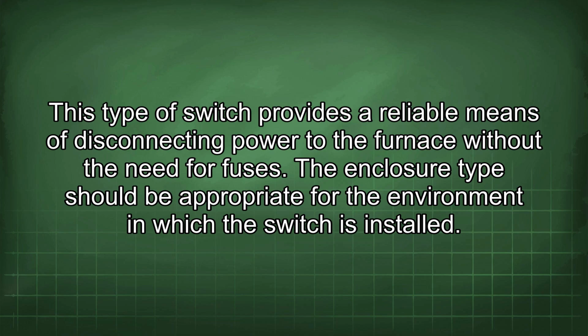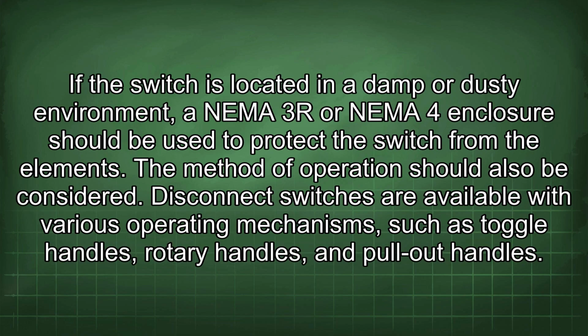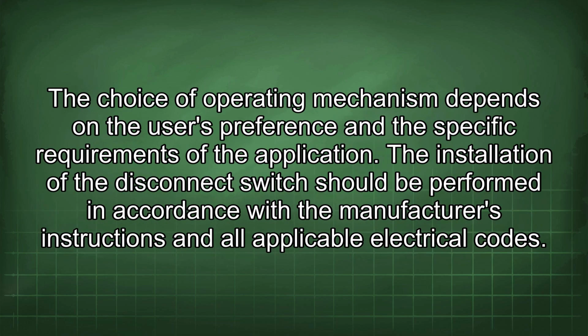The enclosure type should be appropriate for the environment in which the switch is installed. If the switch is located in a damp or dusty environment, a NEMA 3R or NEMA 4 enclosure should be used to protect the switch from the elements. The method of operation should also be considered. Disconnect switches are available with various operating mechanisms such as toggle handles, rotary handles, and pull-out handles. The choice of operating mechanism depends on the user's preference and the specific requirements of the application.